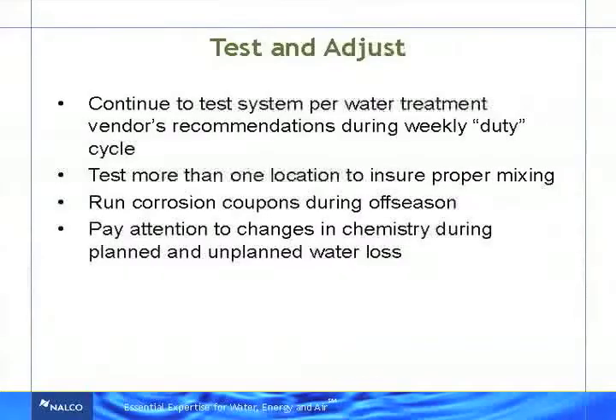Run corrosion coupons during the off season. I don't know if Mike or the other water treatment vendors here would reiterate this, but most of the corrosion I see is actually in the off season because of the lack of circulation. Continue to keep your corrosion coupons in a flooded section to give you an idea of what sort of corrosion you're seeing during that off season and whether or not you're going to have a problem. So keep them in there.